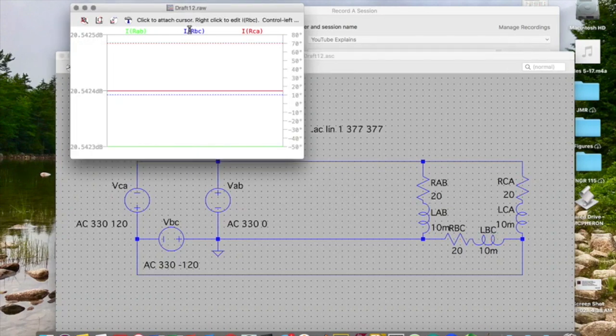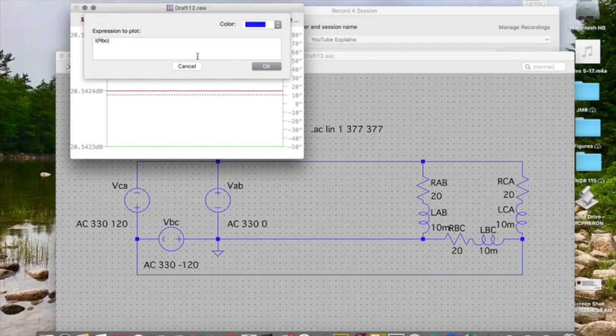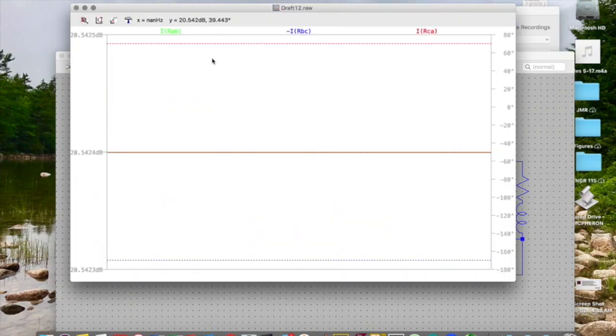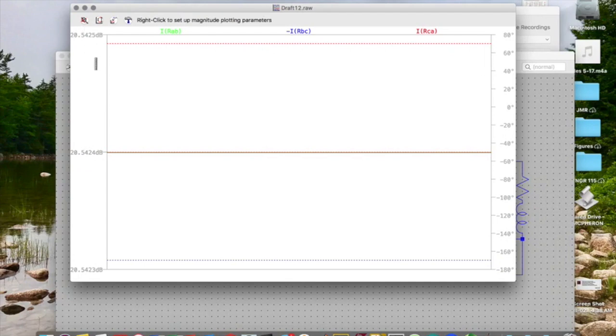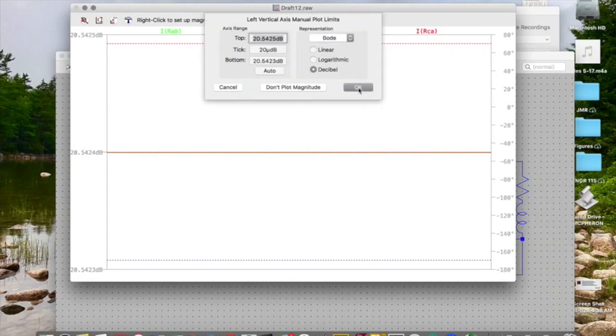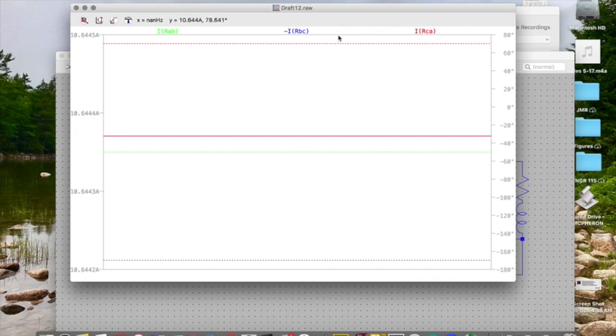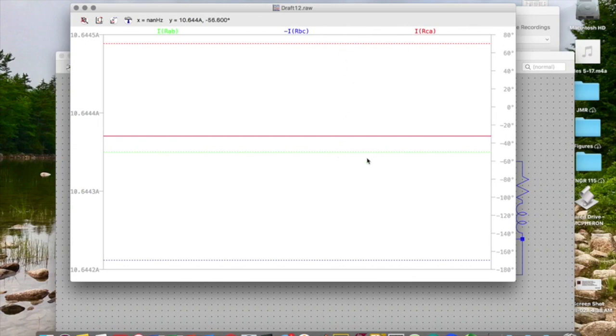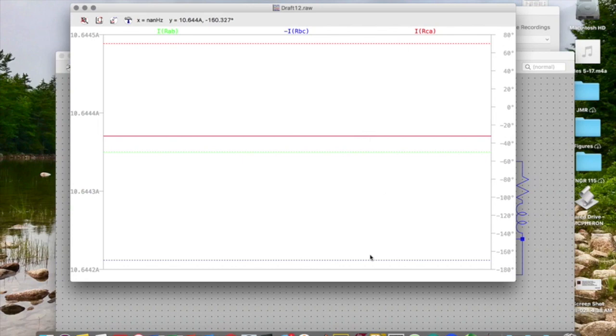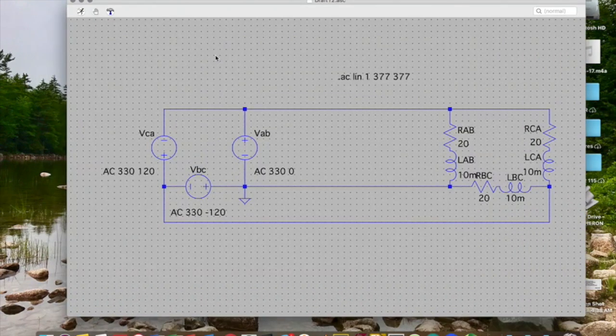So I'll right click up here and I'll choose negative. The last thing that I should be doing here is I should right click on the left hand side. I'm going to change it from a decibel to a linear scale. What I should notice is that every single one of my currents has the same magnitude but the phases are different. You'll see that the phase for CA is at about 70 degrees. The phase for AB is going to be about negative 50 degrees. They're separated by 120. And then the phase for BC is at negative 170 which is about 120 degrees separated.